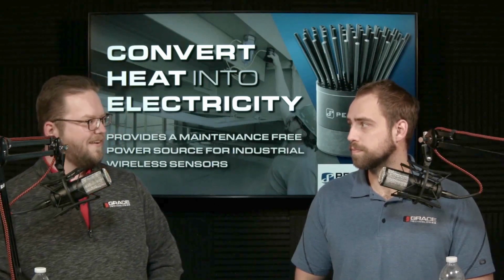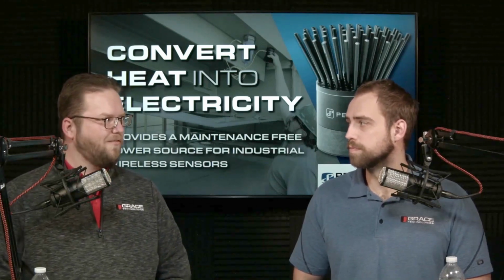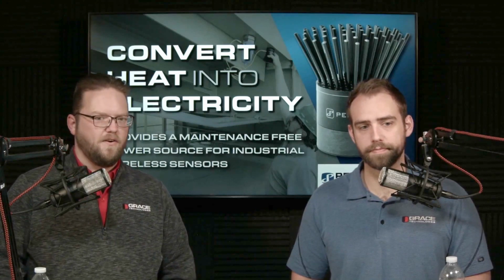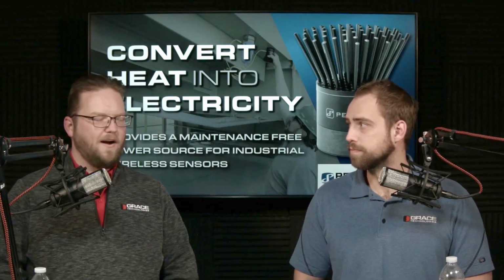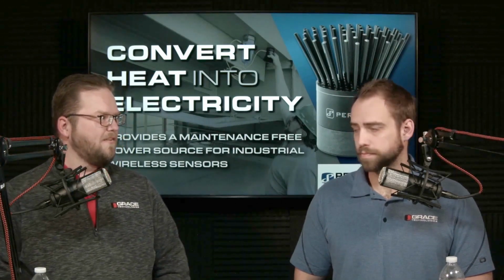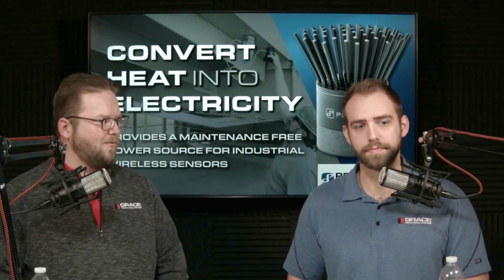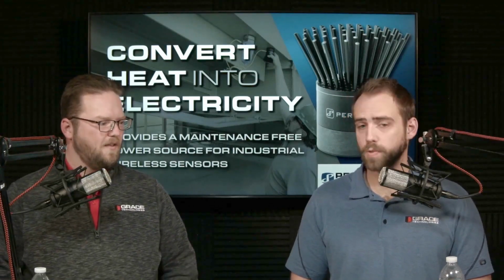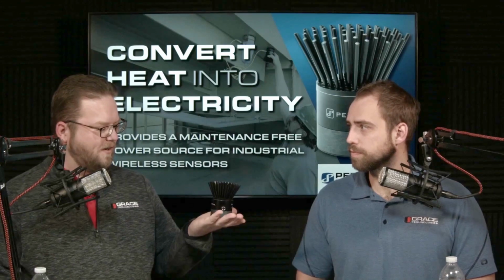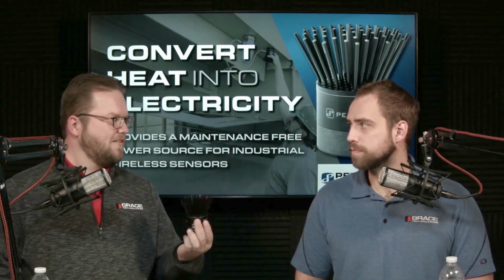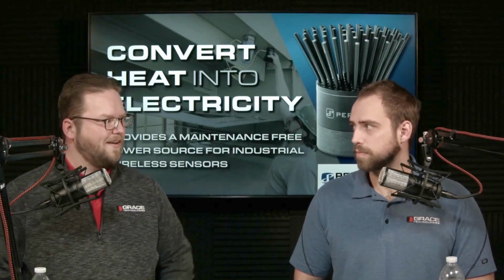It's not going to generate enough to replace a hard-wired 24-volt power source. But for, say, Emerson or Rosemount wireless transmitters, especially in a Class 1 Div 1 hazardous install location, these fit right in. You're able to self-power without running electricity or going out to replace a battery every couple of months.